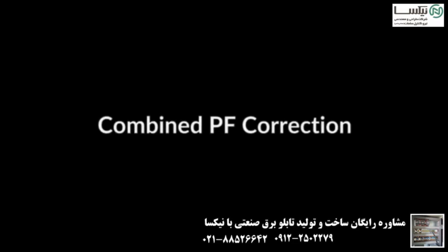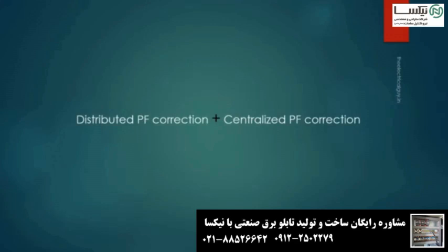Combined power factor correction. As the name suggests, it is the combination of two different methods, that is distributed power factor correction and centralized power factor correction. In this method, distributed power factor correction is used for the large load which runs continuously, and the power factor of small equipment is corrected by centralized power factor correction.